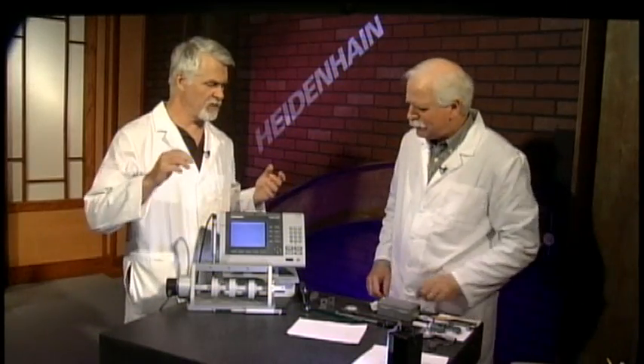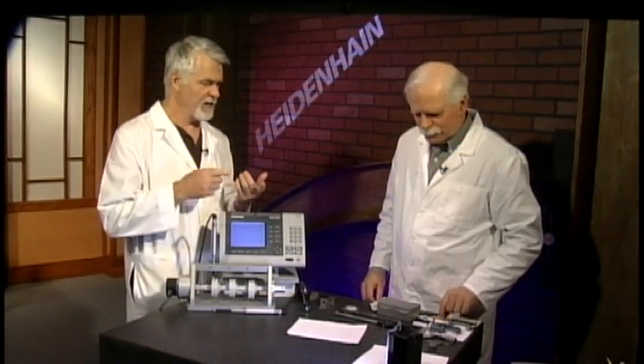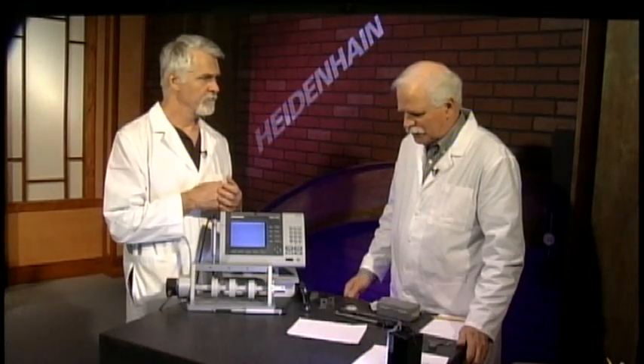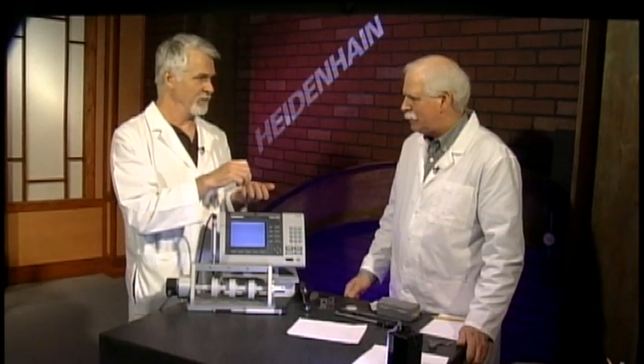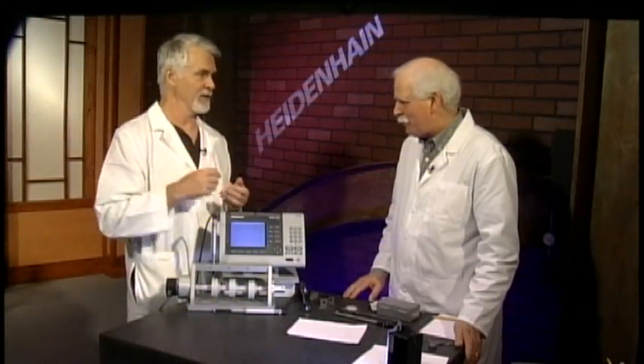One of the things I'm not sure you touched on, but you told me, is that with calipers or micrometers, it's not only technique, but also repeatability, that you do the same thing every time. That's a good point. The pressure you apply to any of these, if you do it the same every time, you're going to be miles ahead. If they're using a ratchet-type micrometer, they get to that final little bit and do 2 or 3 clicks. Do it for all of them, 2 or 3 clicks every time, not 5 clicks one time and 1 click another time. I can't give you a quantity; it might change in one division. It's just consistency, and consistency is always good with these tools.